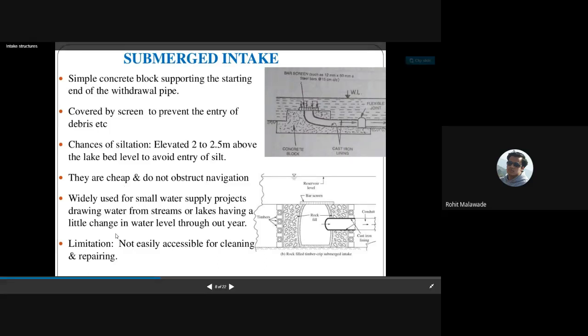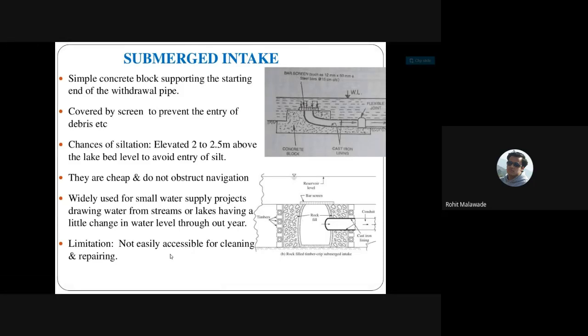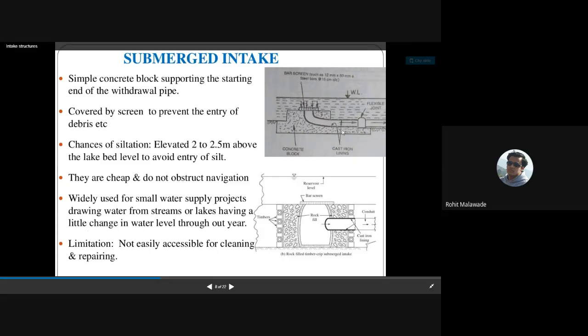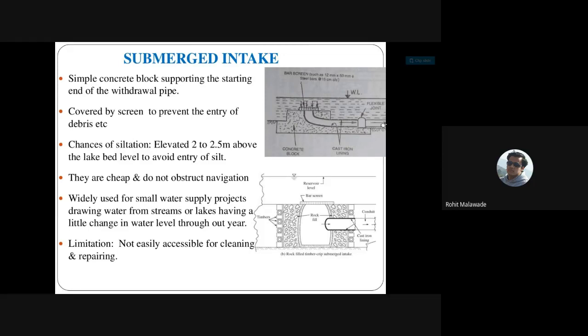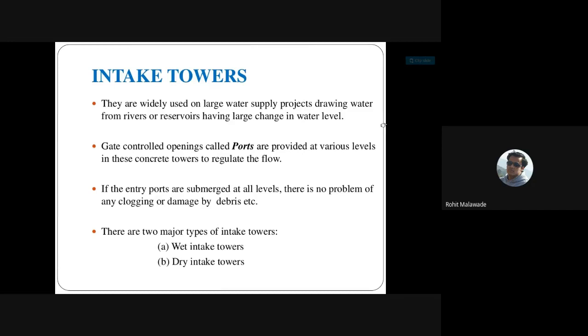Submerged intake structures are used widely in small water supplies drawing water from streams or lakes having little change in water level throughout the year. A limitation is that since the intake structure is completely submerged in water, cleaning can sometimes be difficult.